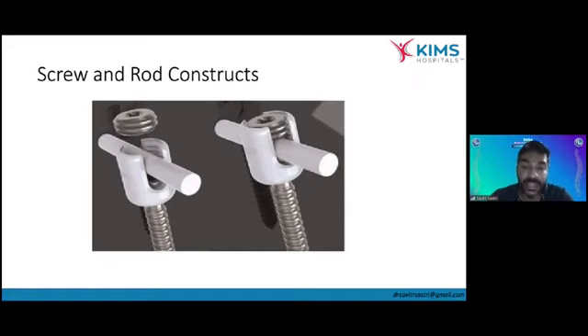The set screws are also very importantly torque-limited, meaning most manufacturers will allow you to tighten them to a predetermined torque—torque being the tightening force. This prevents the screw from over-tightening, which can lead to early metal fatigue and implant failure.